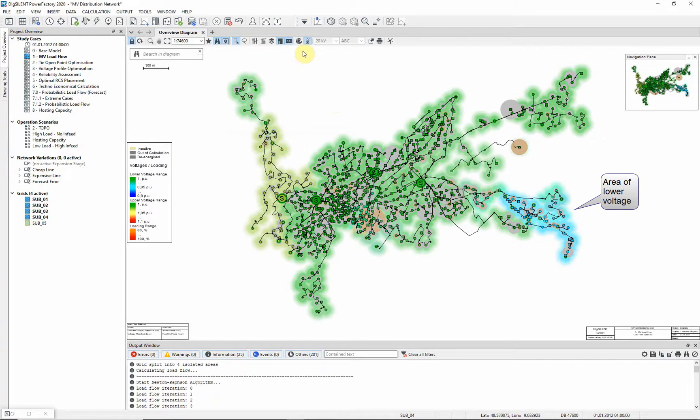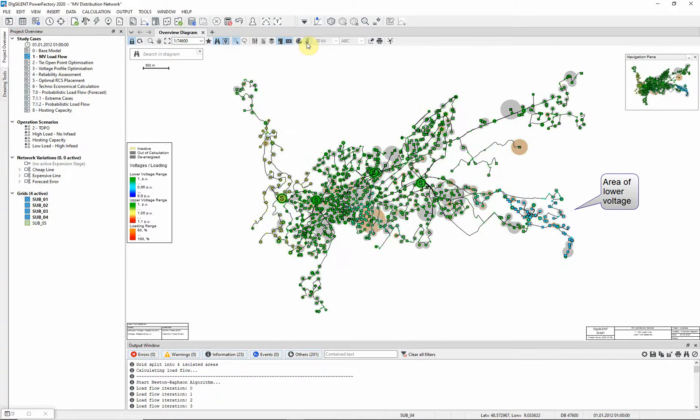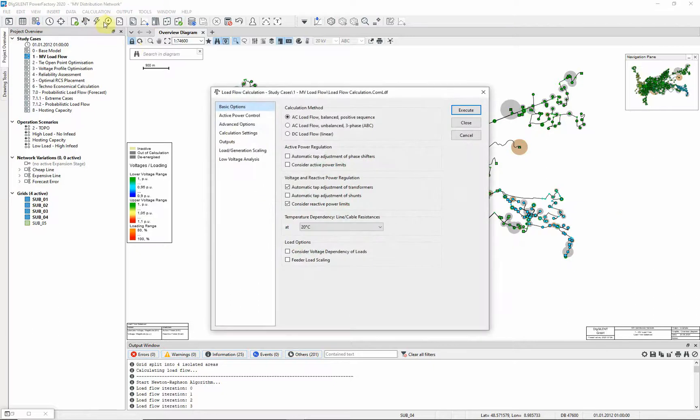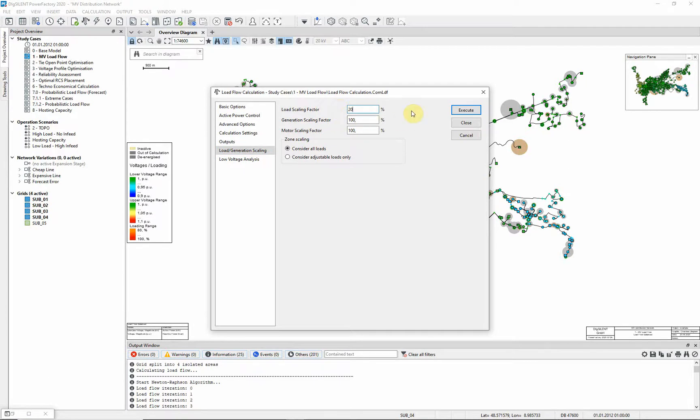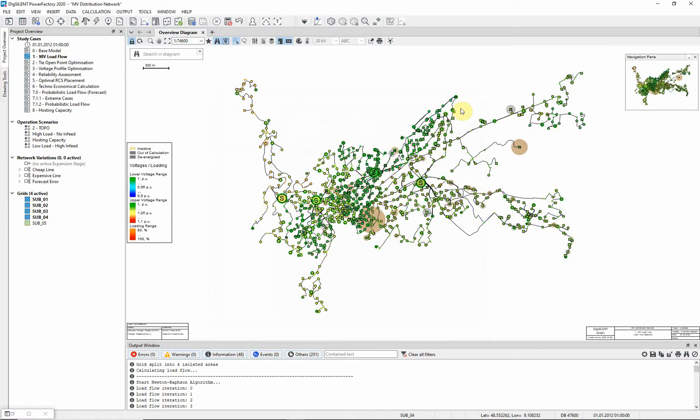Now we will adjust the MV load scaling and examine the effect on the results. Open the load flow command again and change the load and generation scaling page. First, we set up a load scaling of 20% and execute the load flow. You can see that the voltage levels in some areas are higher than before.